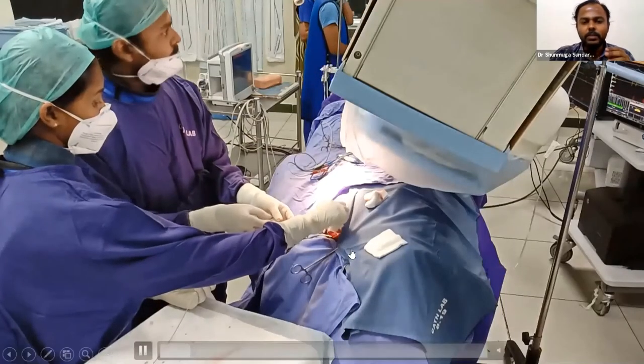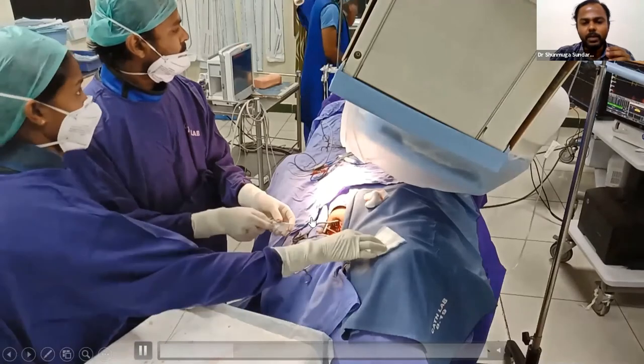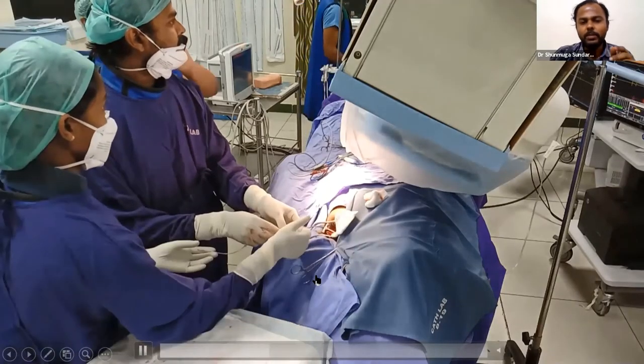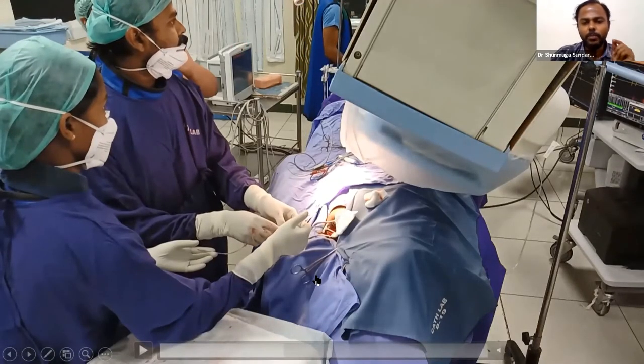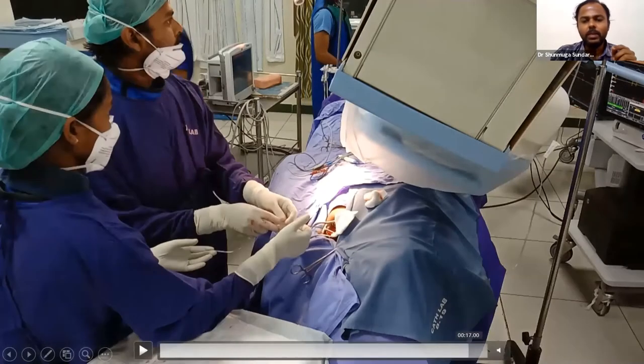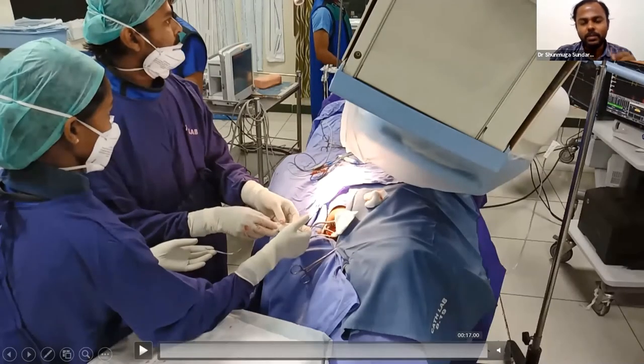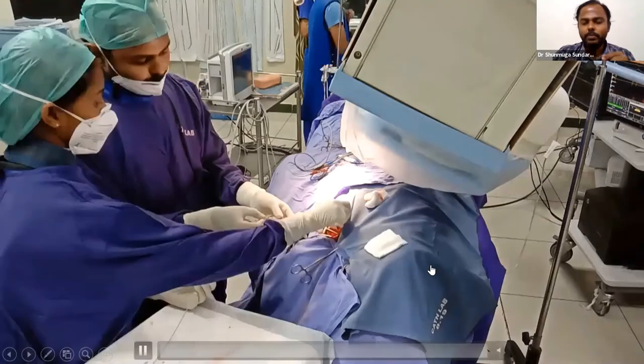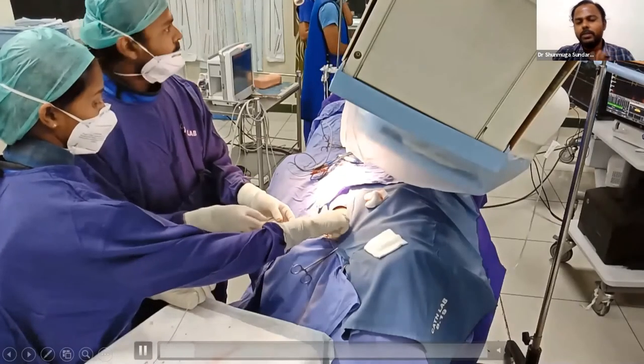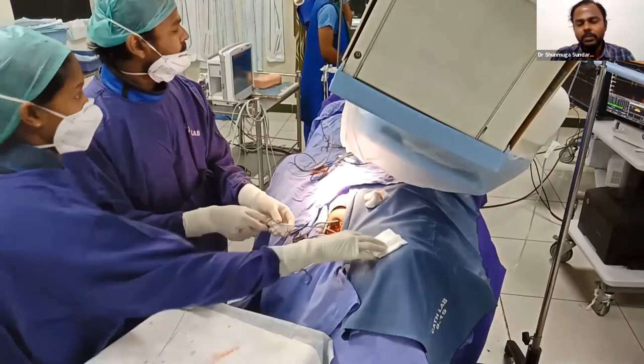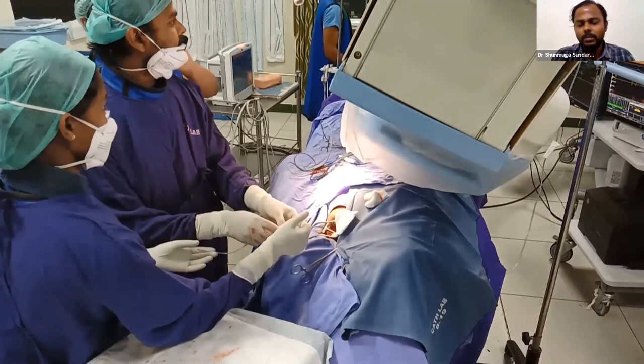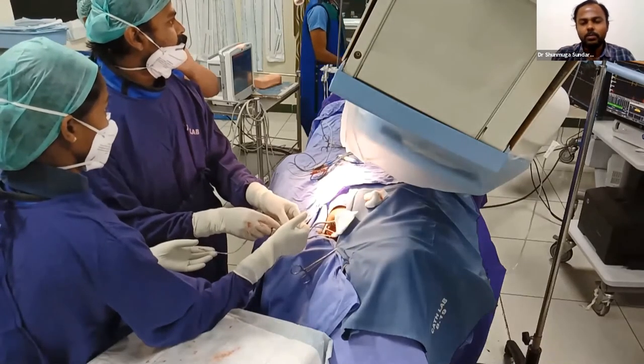Once the target zone is reached, you just put the lead. This is an open helix lead - you cannot put it directly without the sheath, so you have to put it inside the sheath. Once the lead reaches the sheath tip, you expose the tip of the lead outside the sheath. You can see only the tip of the sheath is outside, the tip of the lead is outside the sheath, so only the cathode is just outside the sheath.